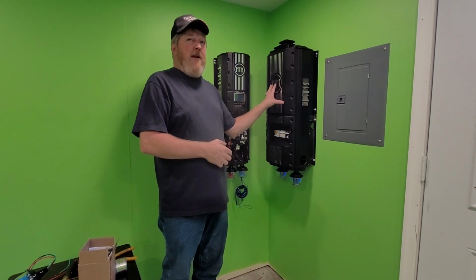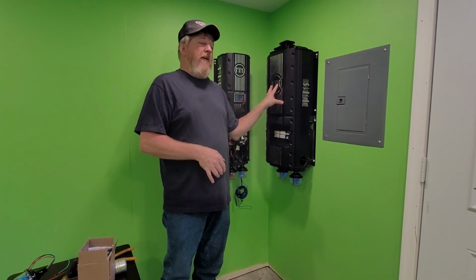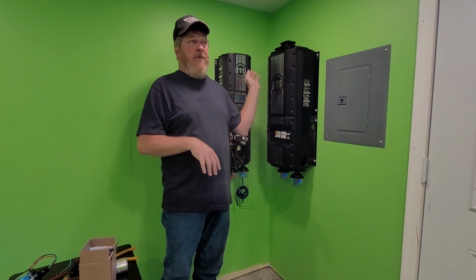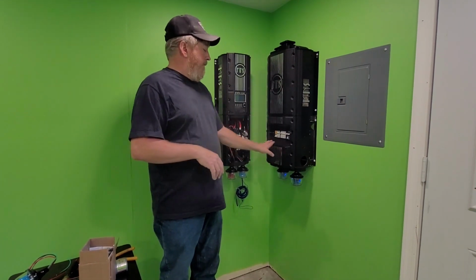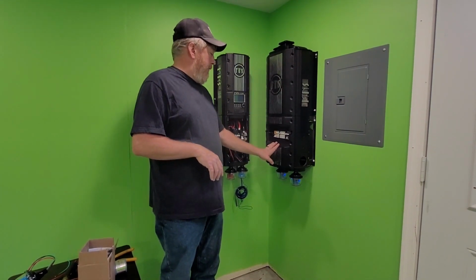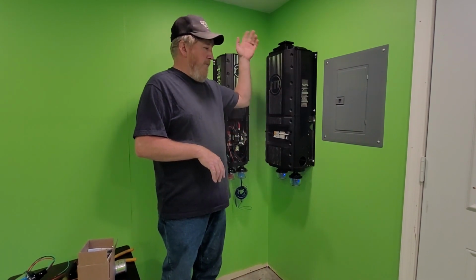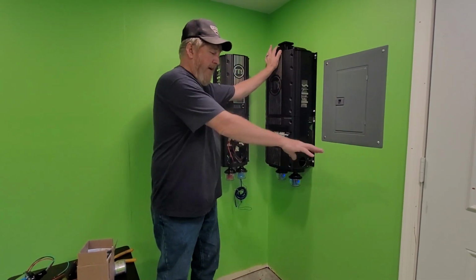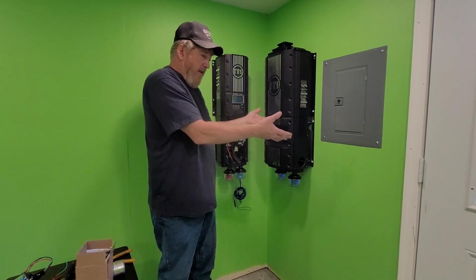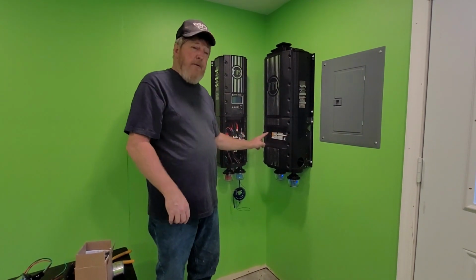So leg 1 was dead shorted to ground in a breaker box in the booth itself. Rosie would try to power that short for about 5 seconds, then shut off leg 1 but keep powering leg 2. But what really impressed me was having all those light bulbs, like 8,000 or 9,000 watts, plus all 4 air compressors, all electrically connected with the Rosie battery breaker off.